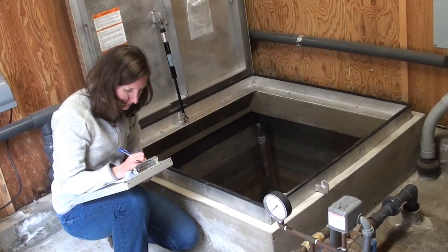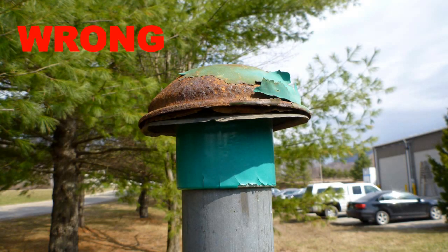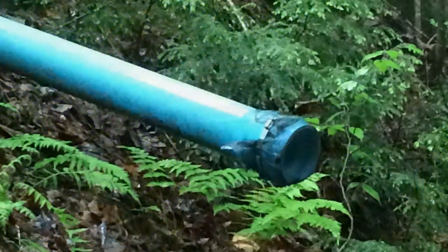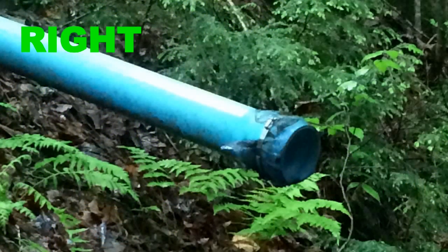Next, take a look at the vent and the overflow of the tank. Make sure they have intact screens of 24 mesh made from a non-corrodable material. This is the same size screen used in window screens. Also, make sure the overflow terminates 12 to 24 inches above the surrounding area and that there isn't a chance that it could become inundated by flooding or runoff.